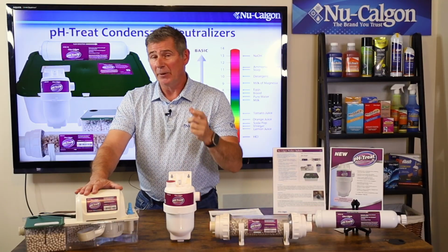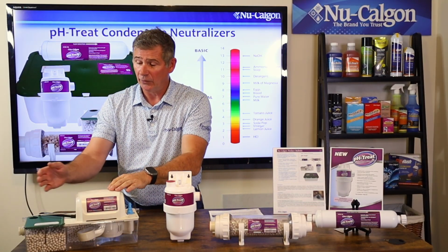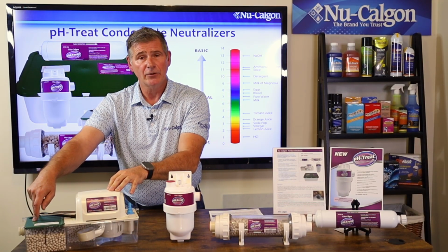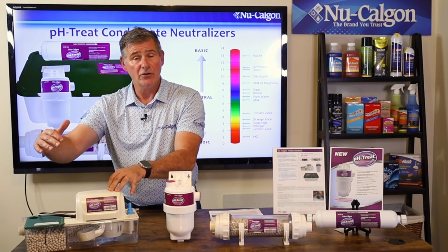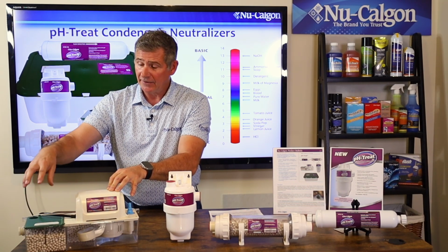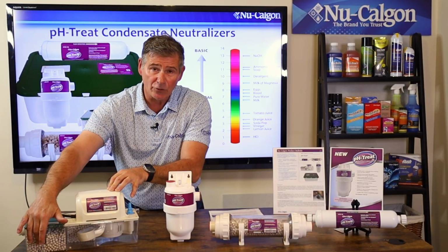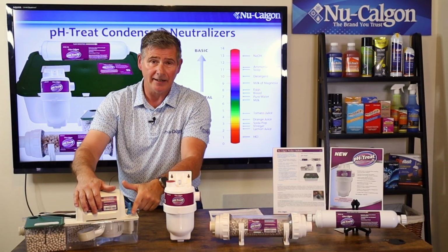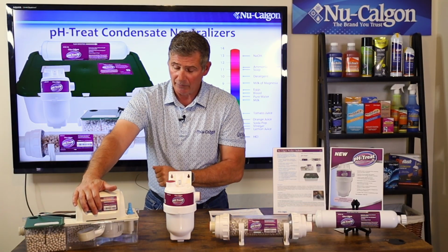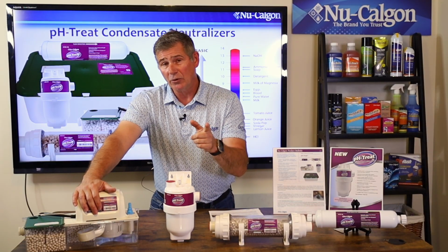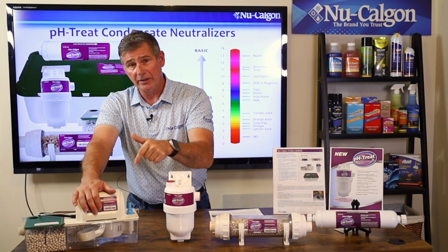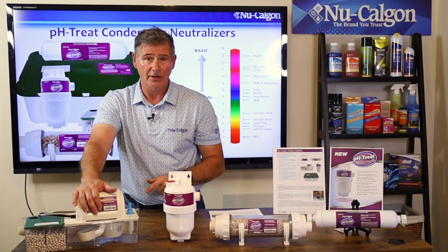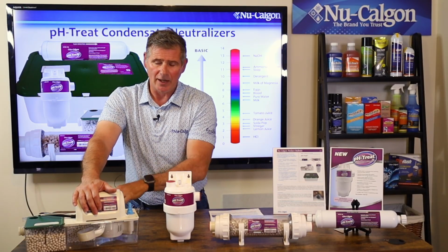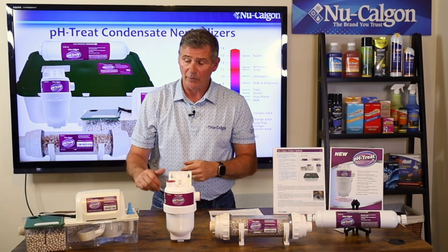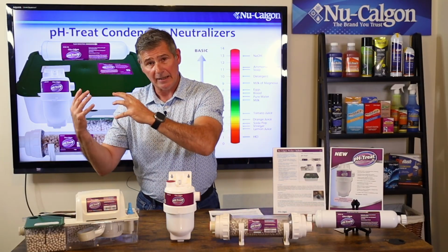But the other really nice feature about this is, on this side over here, you're going to have your condensate water coming in from that high efficiency boiler or furnace. That water is going to get neutralized through the media, and then it's going to end up in the reservoir down there where the lift is. The other thing you can do is you can also plumb in your air conditioning condensate water into this side as well. It doesn't need to go through the neutralizing agent. It can just go directly into the reservoir itself and then get pumped out.